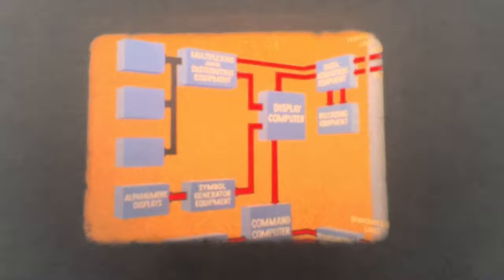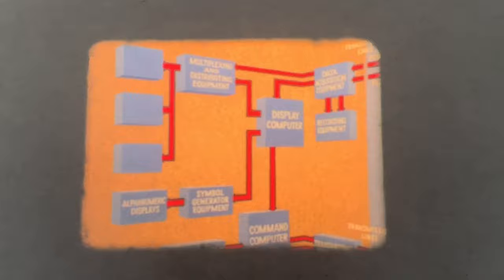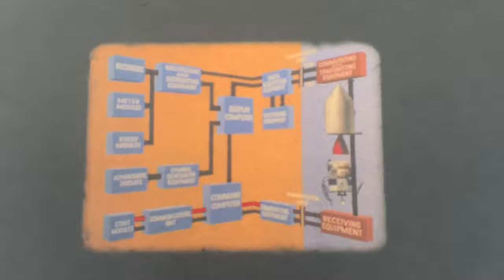The second path of data from the data acquisition equipment transfers digital information to multiplexing and distributing equipment. The data is then sent to three types of display devices on the consoles: recorders, meter modules, and event modules. The recorders are used to log a permanent record of both analog and event information. Meter modules are incorporated in the consoles to give the operator a continuous display of test parameters. The event modules, meanwhile, notify the operator that specific events have occurred. The displaying and recording of the test data at the consoles complete a signal flow of a test command and test data through the ACE system.